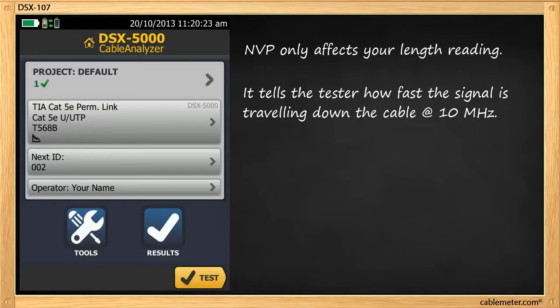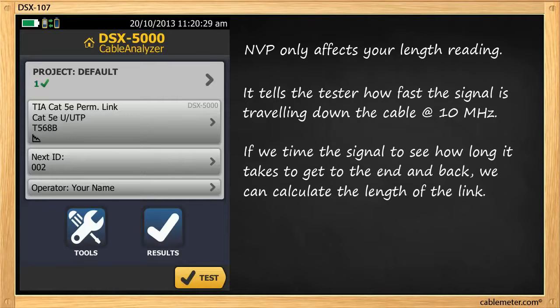The NVP value tells the tester how fast the signal is traveling down your cable at 10 MHz. If we time the signal to see how long it takes to get to the end of the cable and back, we can calculate the length of the cable. Are you ready for some math?